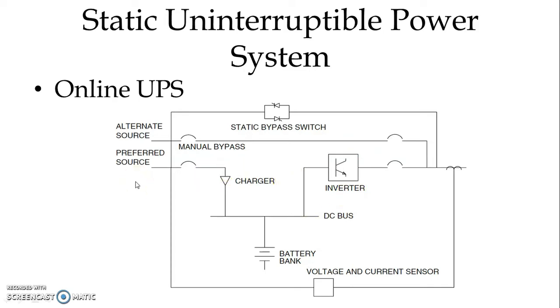In case we require to change to alternate source, in case of loss of power, we have battery bank connected. So as long as battery is not depleted, we have a continuity of the power, else we have to shift to the alternate source of power. We have static bypass switch as well as manual bypass switch. Static bypass switch we use for our preferred source if we want to connect offline, and manual bypass we use to shift our preferred AC supply source to alternate source.